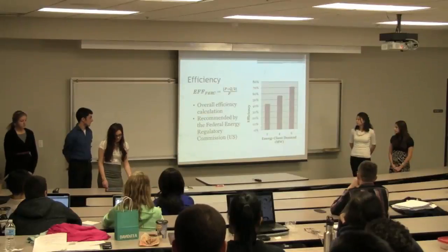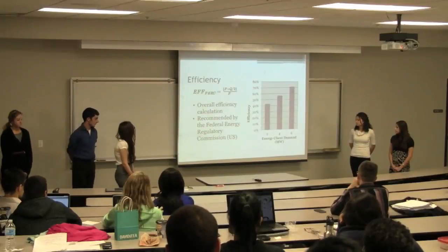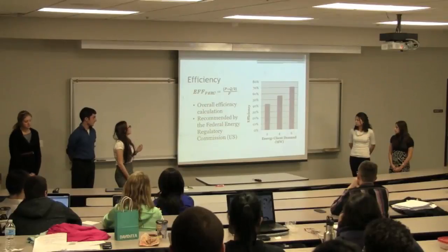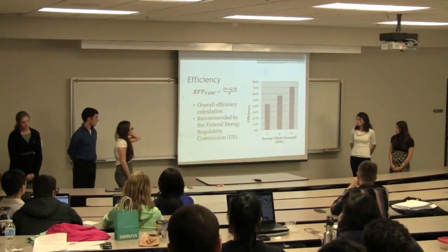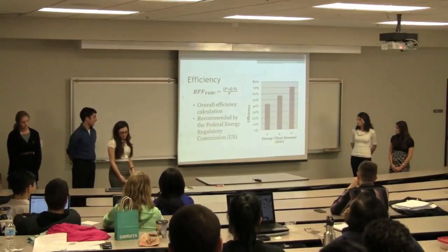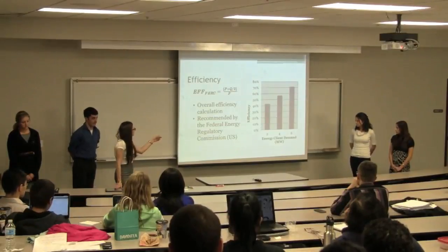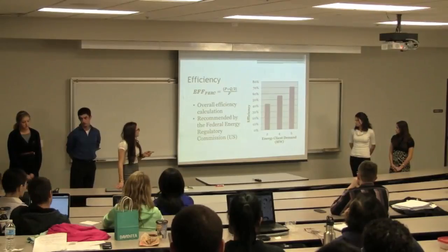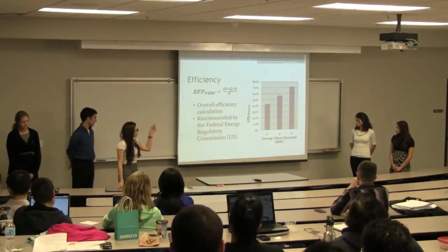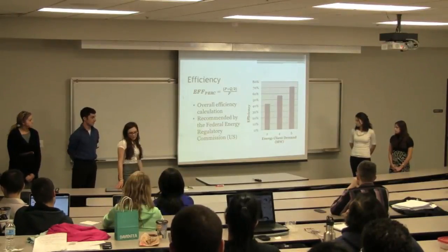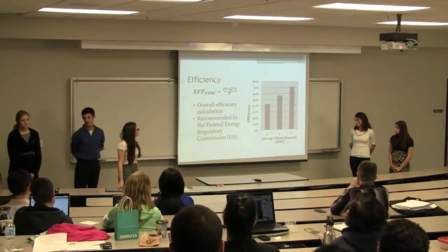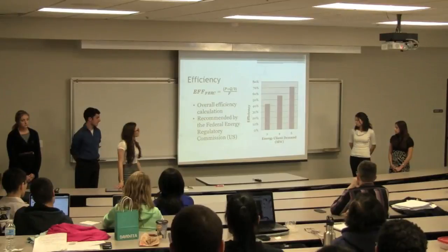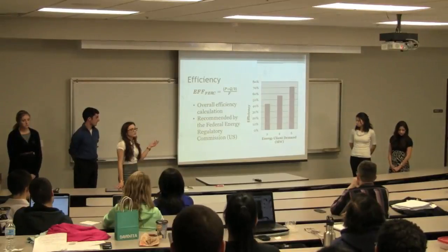And these are just some efficiency calculations I was doing. P is the power output from the plant, Q is the heat output, and F is the fuel input. Basically, I calculated it for a bunch of different cases for the energy plant demand. You can see that the trend is positive with energy plant demand for efficiency. This is because the plant is optimized for steam production and electricity generation is just a possible byproduct. So if you're using more steam, your efficiency overall is higher.